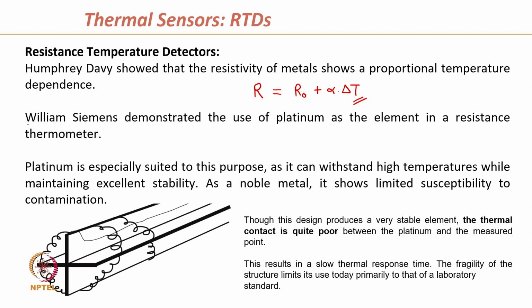And William Siemens demonstrated the use of platinum as an element in a resistance thermometer. So, he used a platinum wire as an element to make an RTD. Why is platinum specially used? Because it can withstand high temperatures. You can use the platinum wire to measure very high values of temperature. It can withstand them without melting and still maintain excellent stability even at those high temperatures.